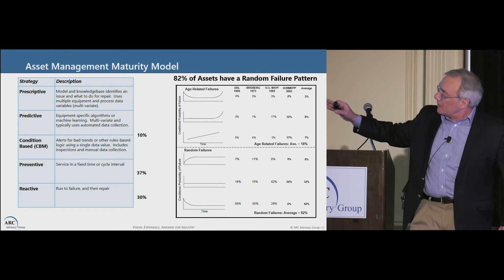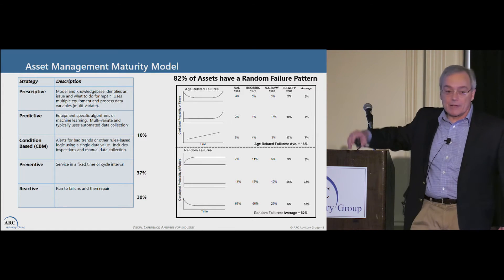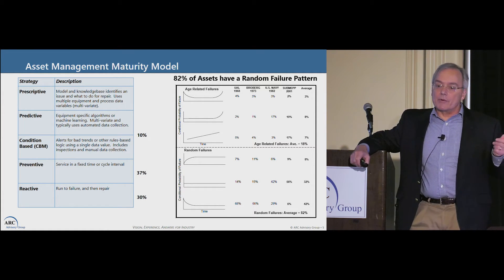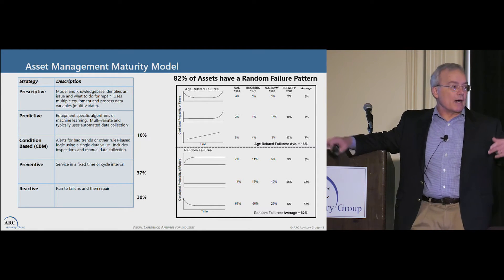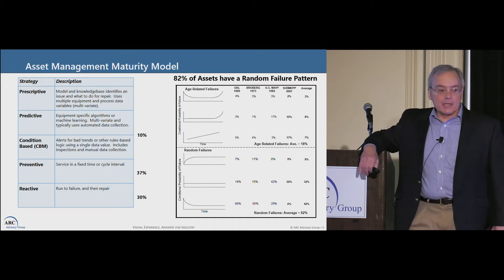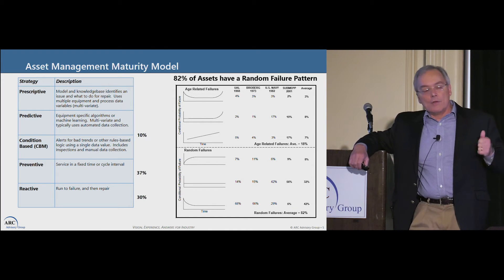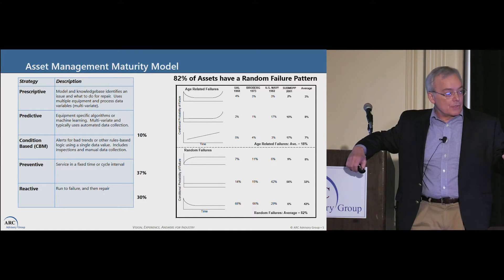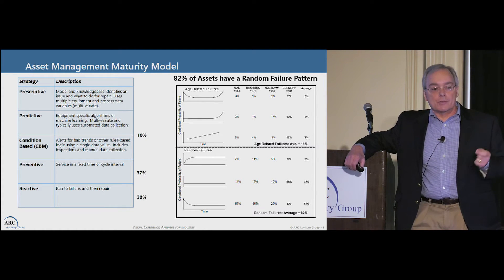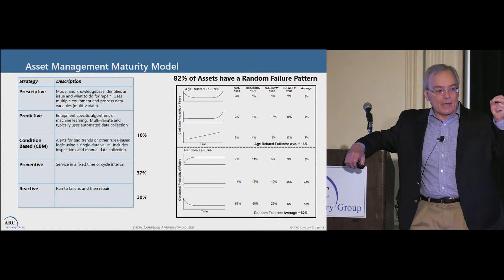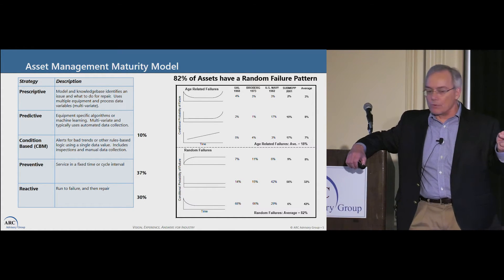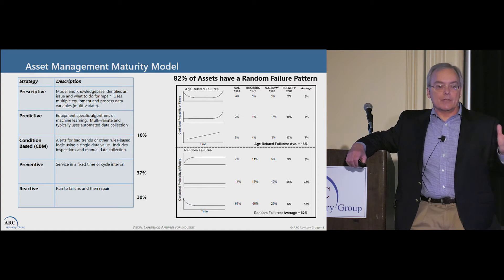This chart — I'll give you the short form. The numbers on the left in the middle — 30%, 37%, 10% — tell us where we are now. We did a survey and asked maintenance managers what types of work orders they issue. That's why this doesn't add up to 100%, because there are others beyond what's listed here. The dominant one is preventative maintenance. One key point: if you move from preventative maintenance to predictive or condition-based maintenance — this is a study done by Shell — your maintenance costs on average are cut in half. That has to do with labor and also MRO materials. The reason is you're doing the maintenance when it is needed, at the point when an anomaly is found and we know maintenance is required.